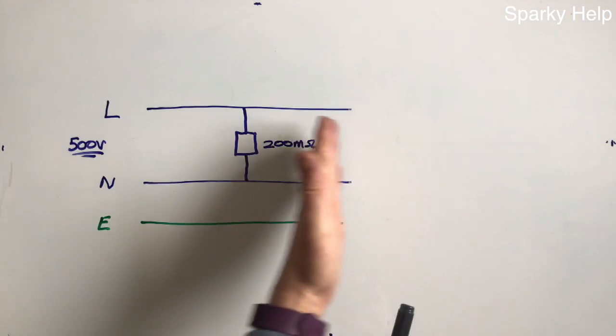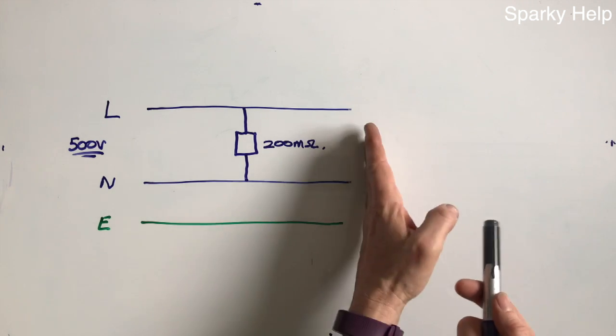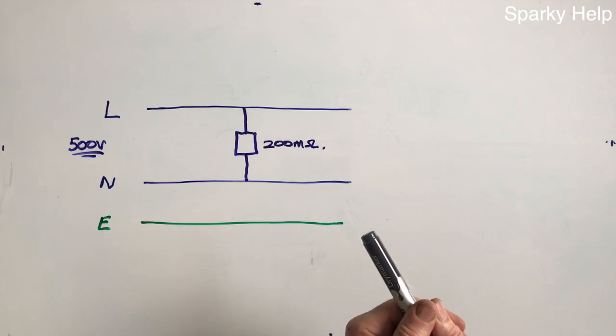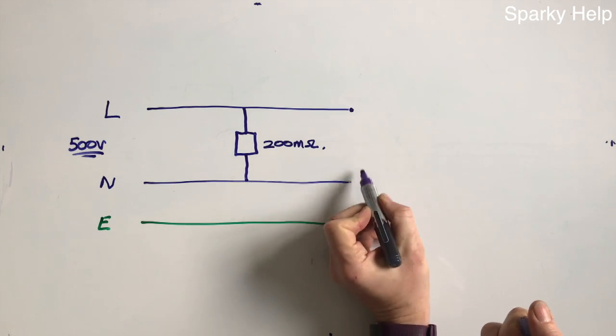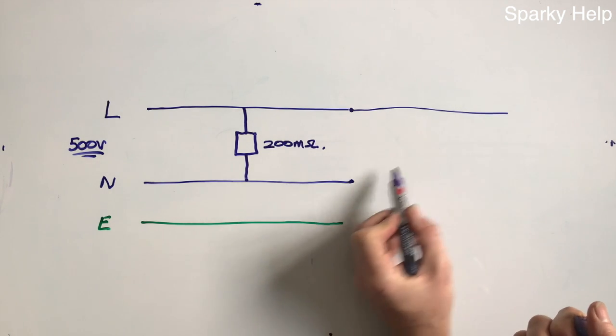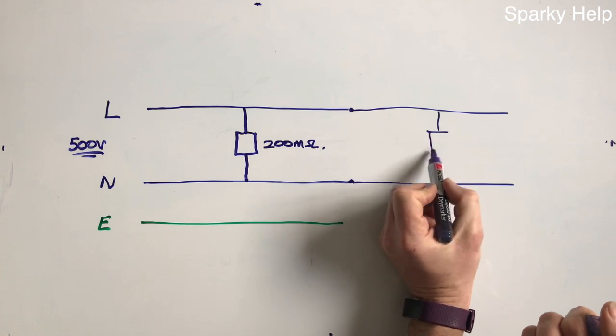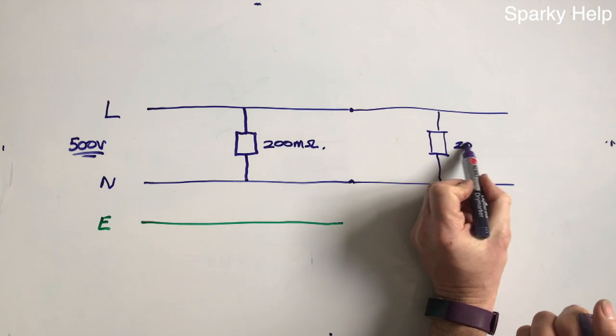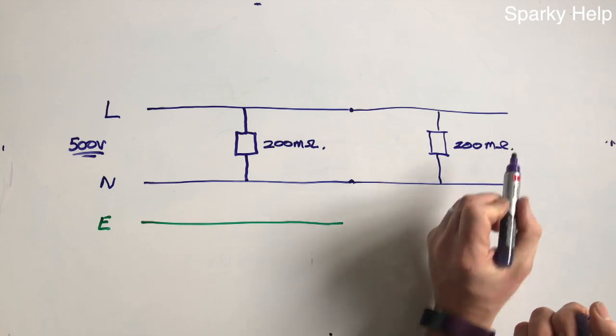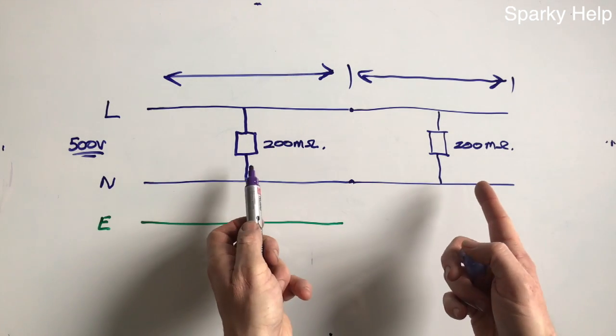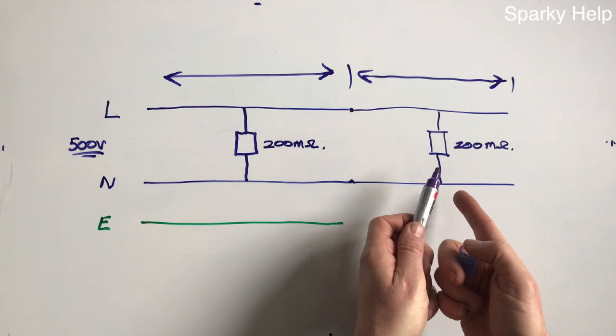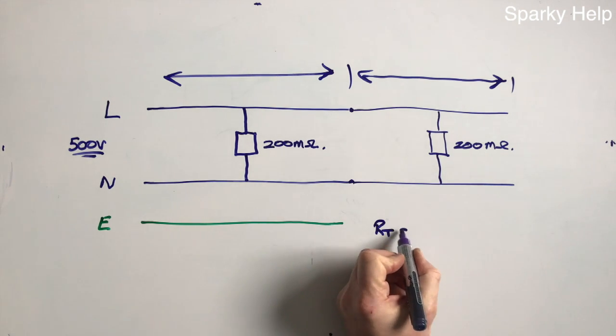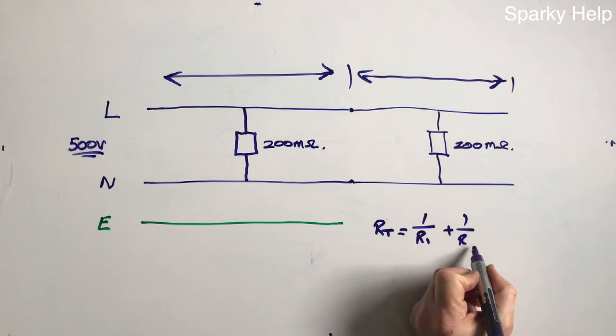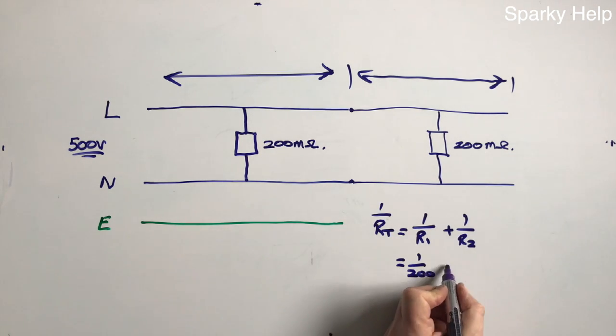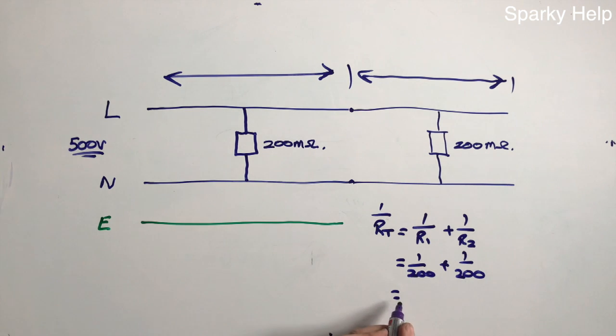So you've installed this circuit now, and then the client says, I'd like to double the length, or you want to add another socket, or whatever it happens to be. So you're going to join onto this cable, and you might put exactly the same cable on again. And the exact cable from that manufacturer will have an insulation resistance too. So we have 2 lengths of cable joined together. Basically what we've now got is parallel resistances. So in insulation resistance, the formula is a parallel resistance. It's that. Okay, so it becomes 1 over 200 plus 1 over 200, and 1 over your answer as well, which equals, in this case, half of that.